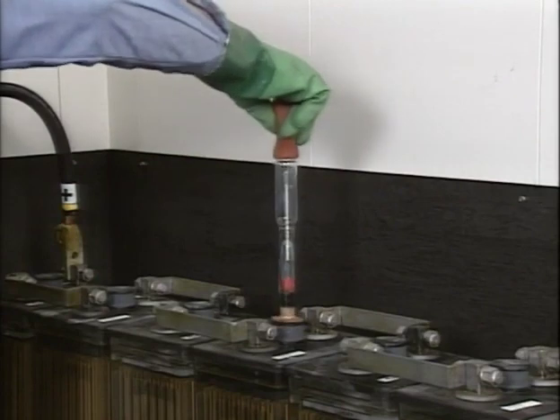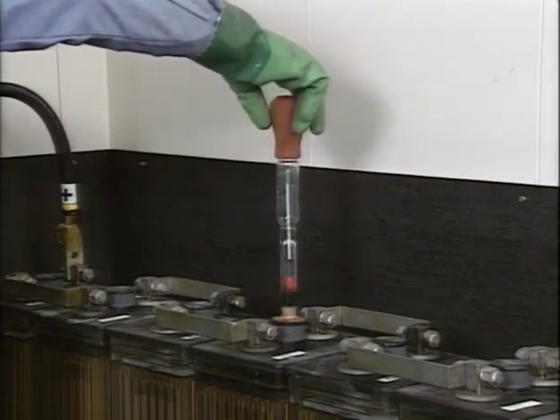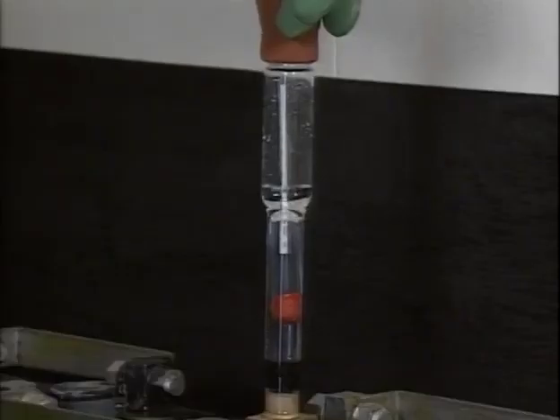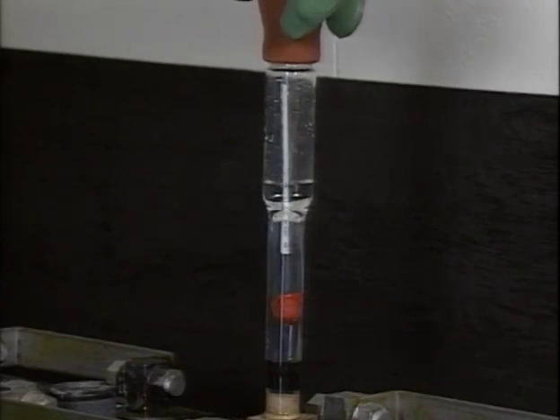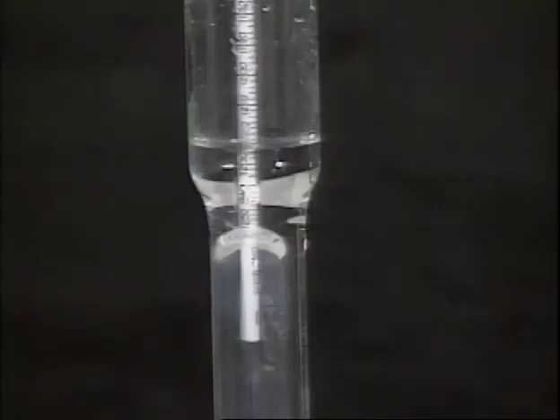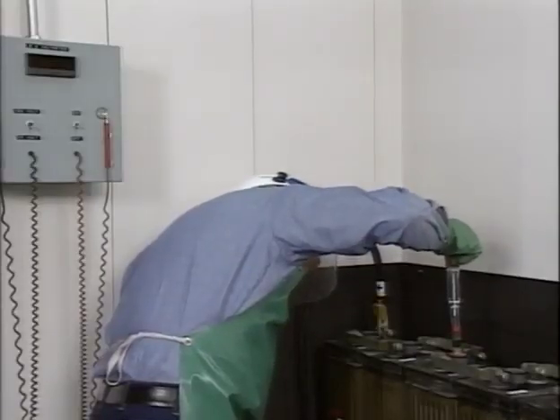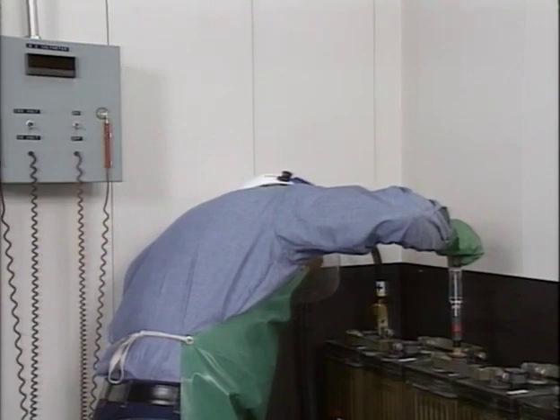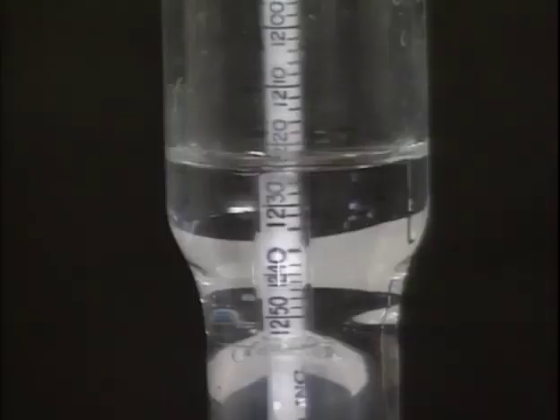While a sample is being drawn, the syringe is held vertically so the float doesn't touch the sides of the barrel. Enough electrolyte is drawn to lift the float off the bottom of the barrel, but not so much that the float hits the top of the barrel. If the specific gravity is high, the float will ride high in the sample. If the specific gravity is low, the float will sink lower into the electrolyte. Once the float steadies, the specific gravity is read off the scale at the surface of the electrolyte. The specific gravity reading here is 1.222.